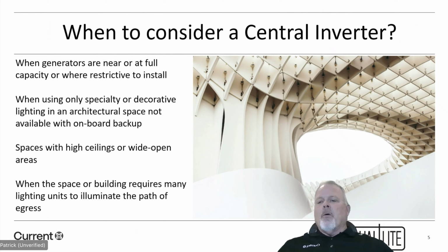When generators are near or at full capacity or where restrictive to install. You'll see this oftentimes in data centers, for example, or healthcare environments, hospitals specifically. When using only specialty or decorative lighting in an architectural space, not available with onboard backup. So this is pretty obvious. These are smaller fixtures. They don't have the room for a battery backup, but they have to be used to make sure we maintain the proper path of egress. So this would be a good example, again, to use an inverter.